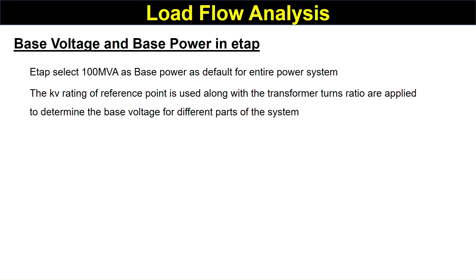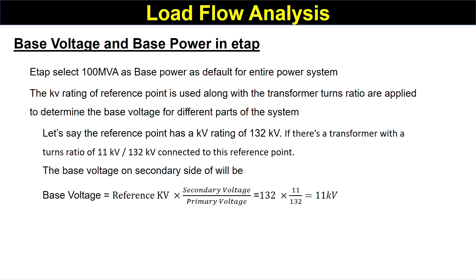Let me explain this with an example. Let us say the reference point has a voltage rating of 132 kV. If there is a transformer with a turns ratio of 11 kV / 132 kV connected to this reference point, the base voltage on the secondary side will be: base voltage equals the reference value multiplied by secondary voltage divided by primary voltage. Here, the reference value is 132 kV, the secondary voltage is 11 kV, and the primary voltage is 132 kV.